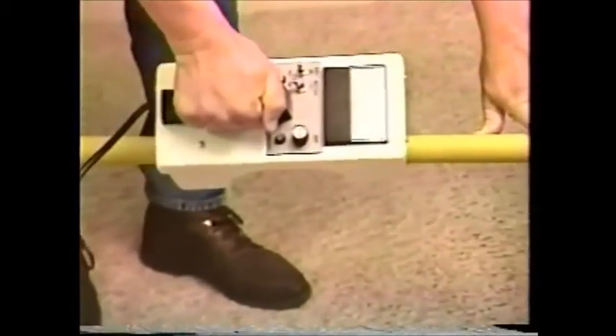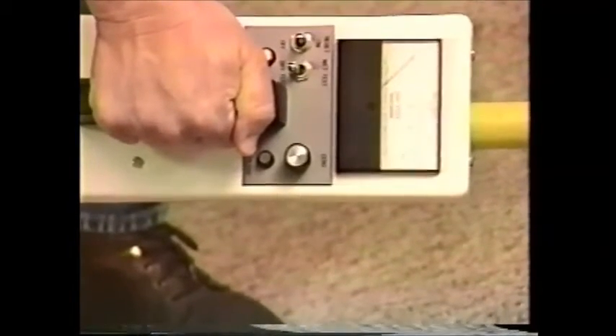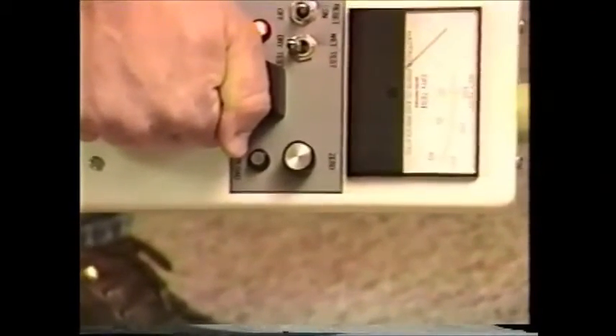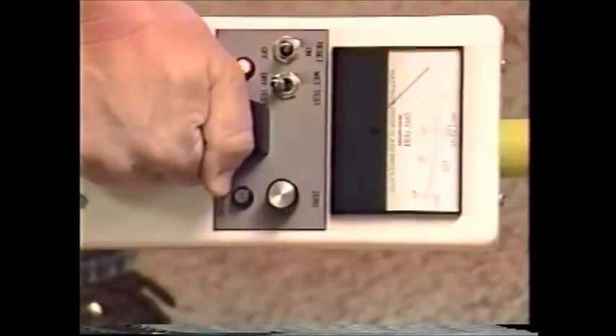Seldom will a visual inspection of a dry stick yield any useful indication as to its dielectric condition. The stick being tested has been returned from the field. While it looks contaminated, its dielectric value is still quite good.